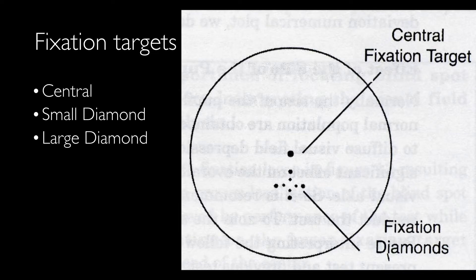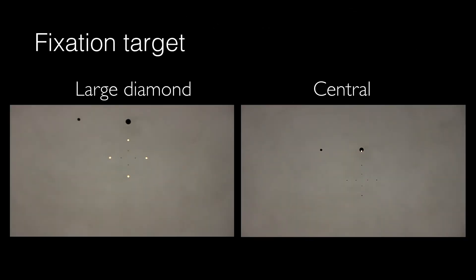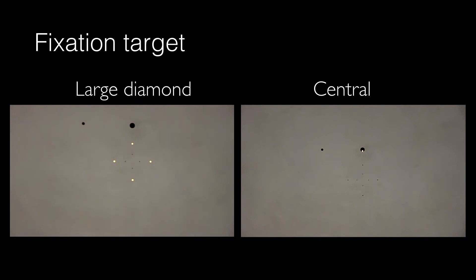In the Humphrey machine we have three fixation targets: central, small diamond, and large diamond. Generally we use diamonds in those patients with poor central vision, like age-related macular degeneration. This video presents the large diamond on the left side and central fixation target on the right side. The patient is supposed to look at the fixation target all the time that the stimuli are presented.